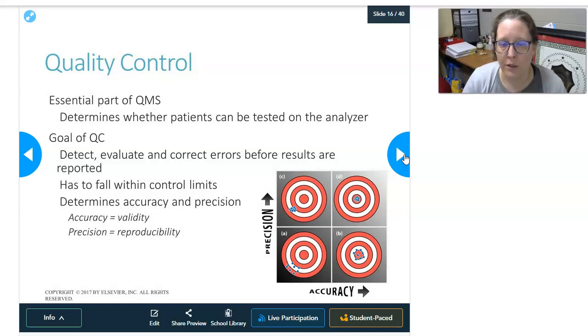So it has to fall within control limits, which we saw in the assayed controls were determined by the manufacturer, and the unassayed have to be determined by the lab. Those control limits are usually the mean plus and minus 2 standard deviations. That usually gives you a range of concentration that is listed as, 100 milligrams per dL to 120 milligrams per dL or something like that. So when you get a result, say my quality control result is 110, well, that is within the range. I'm good to go. Oh, it's 125. That's too high, I'm outside, so we need to troubleshoot that. So it makes it very easy for you to see if your controls are in or out.